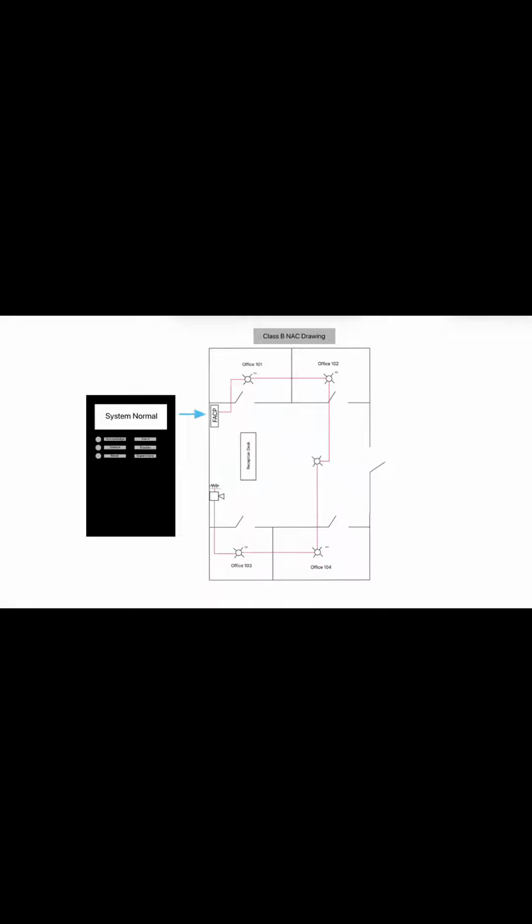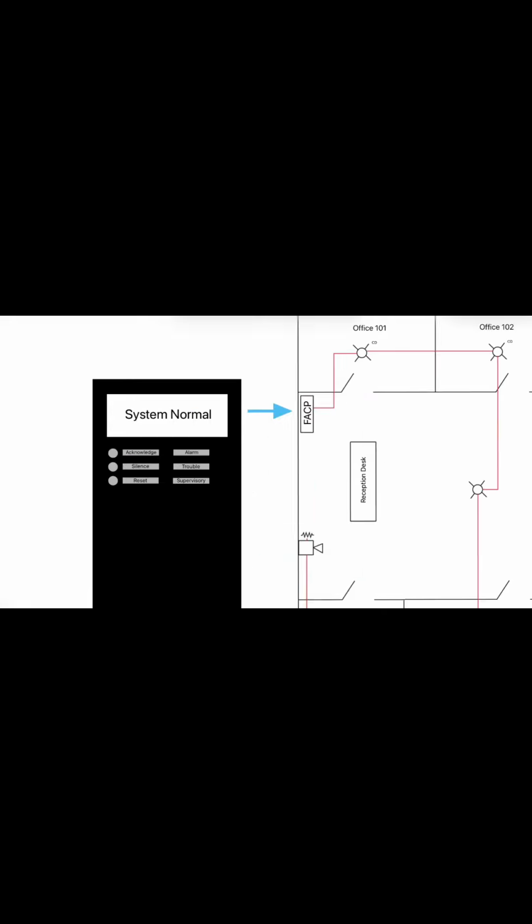Generally, different manufacturers of fire panels use different end-of-line resistors. They are included with the fire panels. Here is the fire panel, and we can see that the system is normal. However, once we remove the end-of-line resistor, the panel will show a trouble code.